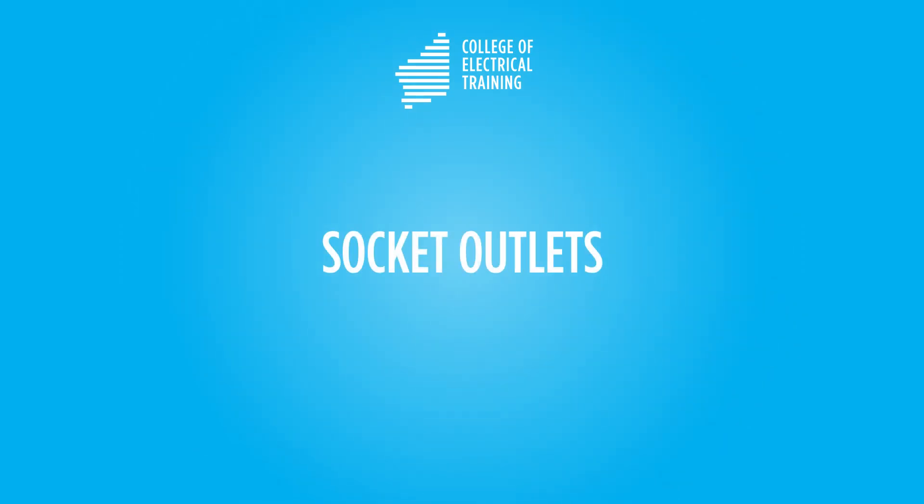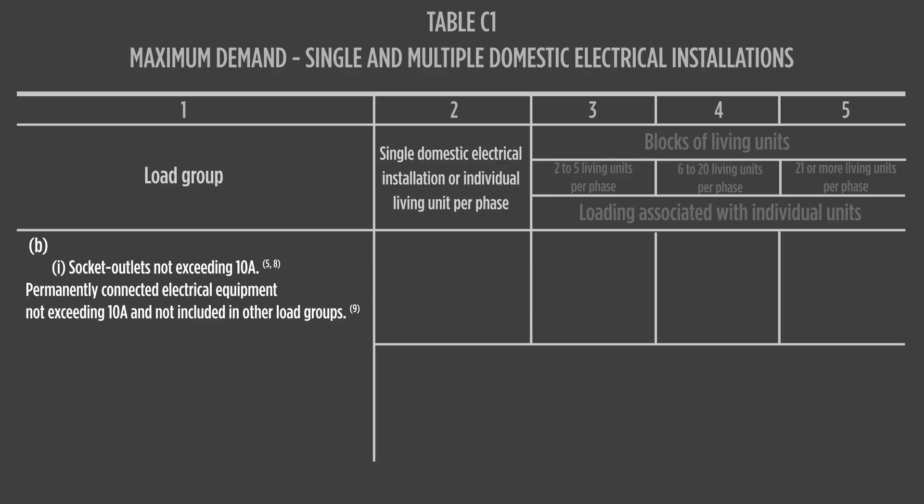However, lighting load in a domestic dwelling does not contribute significantly to maximum demand, and this option can be ignored. For socket outlets, unless installed for a specific purpose, it is hard to determine the loading on a 10-amp socket outlet, so the calculation applies a point allocation: 10 amps for 1 to 20 points, with 5 amps for every additional 20 points. 15 and 20 amp socket outlets are allocated current values for calculating maximum demand, as these are installed for specific reasons.